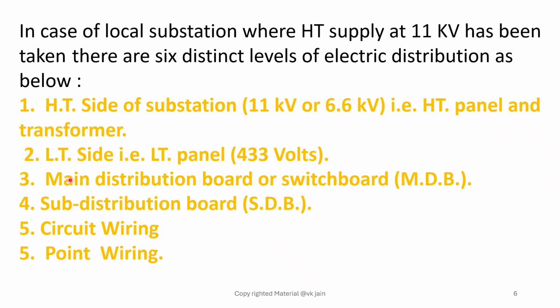Next is the main distribution board or switchboard, MDB. The next is the sub distribution board, SDB, and this SDB may be 4-way, 6-way, 10-way, and 12-way, and each way of a 4-way represents 12 circuits, 6-way represents 18 circuits. So go on multiplying the number of ways, and as much kilowatt will be consumed by them. The next is circuit wiring, and next to that is point wiring.